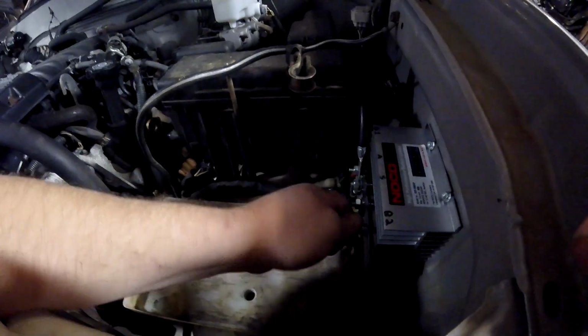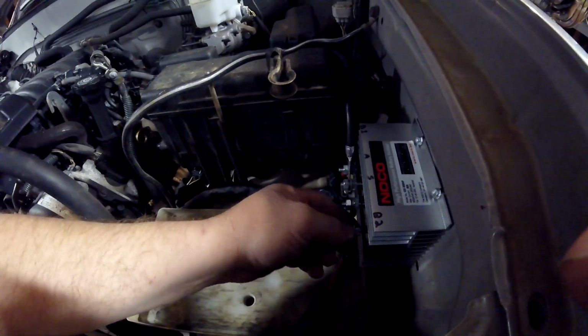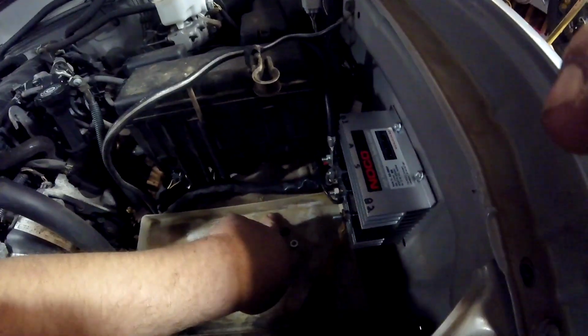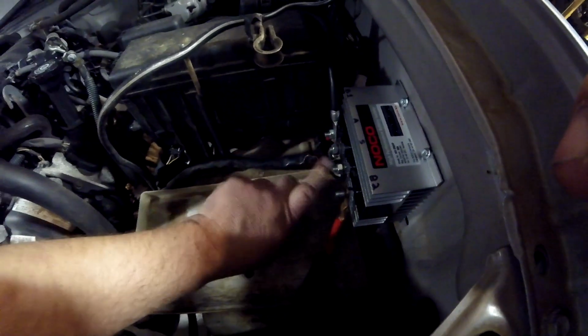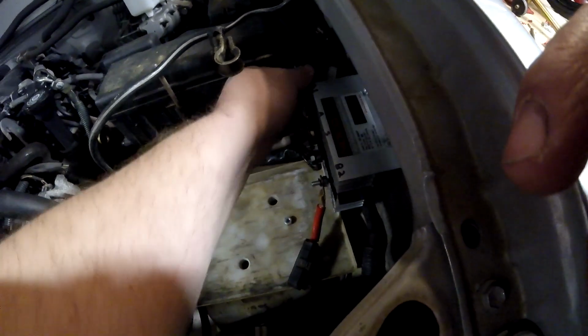Now, another little trick I do before I torque this down for the final time, guys, is I wrap that lug with tape. Okay? I didn't do it over there, and I should have. So while I'm here, I'm going to pull that apart, and I'm going to wrap these lugs, because if that bent back just the slightest bit, if somebody reached in there with a tool and bent it back, yeah, it's firm and it shouldn't.